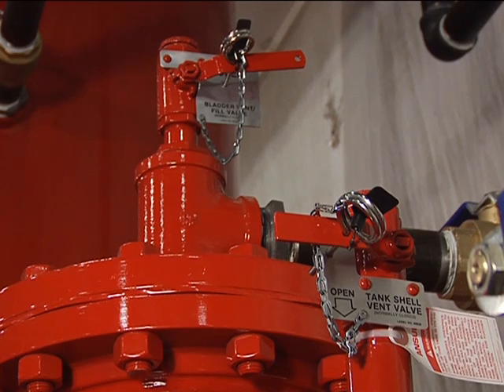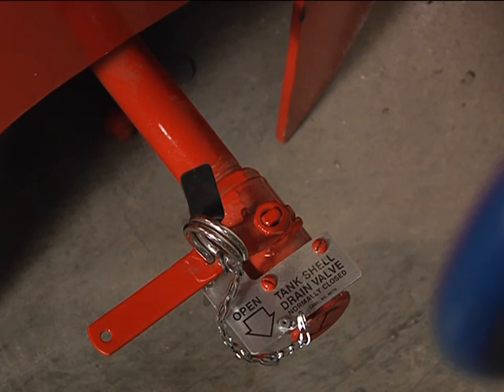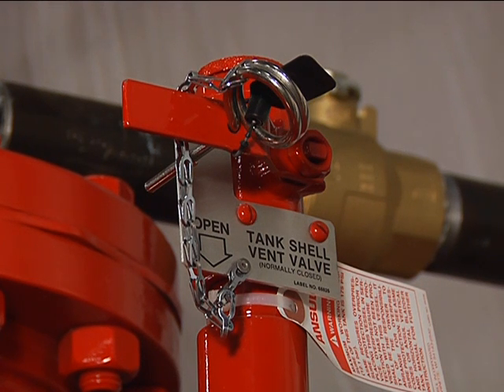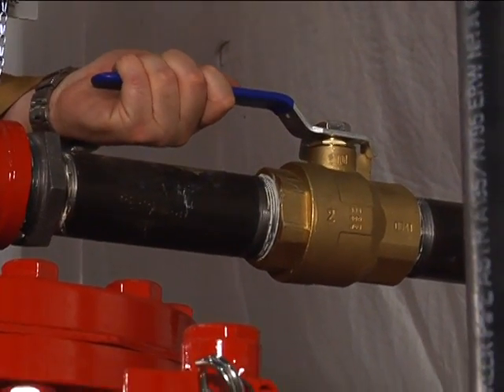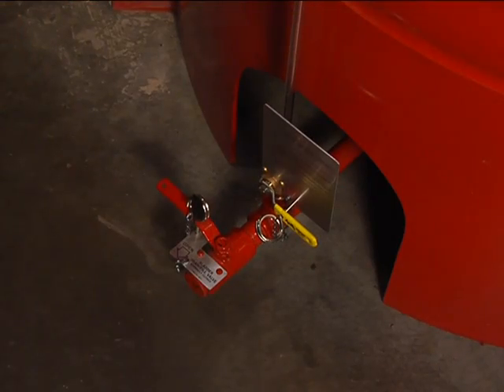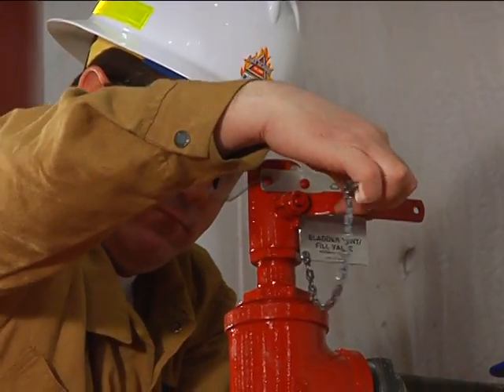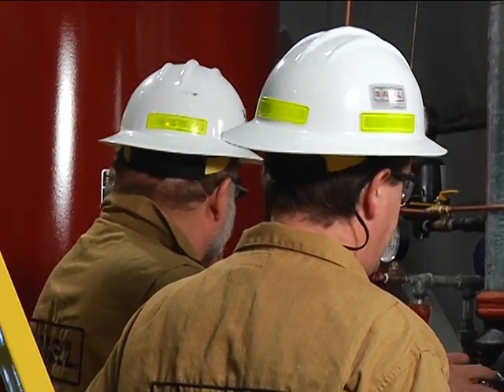The next step is to return the bladder tank valve handles to the following operating positions: water inlet valve open; tank shell drain valve closed; bladder drain fill valve closed; tank shell vent valve closed; bladder vent fill valve closed; concentrate isolation valve to normal operating position; and if provided, sight gauge valve operating. Insert the ring pins through the valve handles into the brackets and install the visual inspection seals. A maintenance examination should be performed at this time. Finally, record the date of placement in service and instruct personnel on operation of the system.